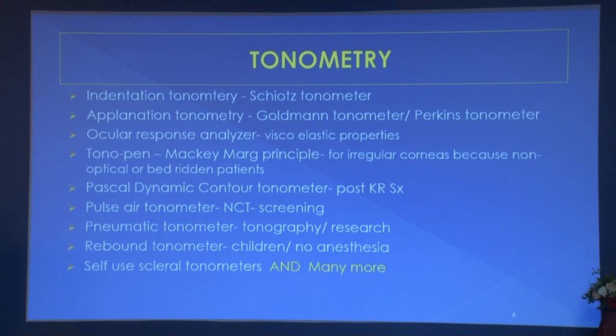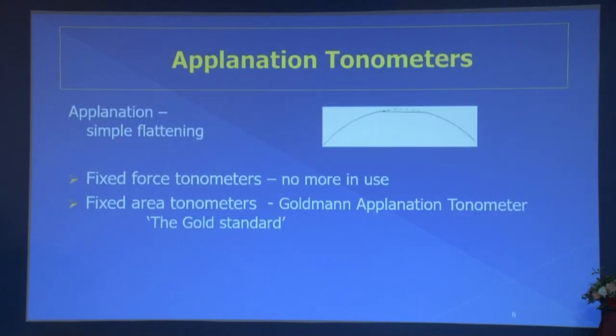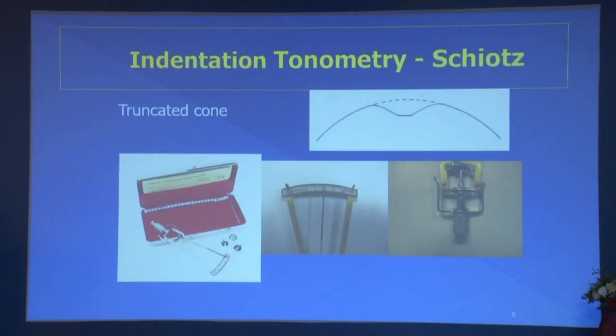Tonometry is basically indentation and applanation, though other types are now included. Many instruments are coming up with specific indications. For applanation tonometry, fixed force tonometers are no longer in use — only fixed area tonometers are used now, and the gold standard is Goldmann applanation tonometry. Indentation tonometry is problematic when scleral rigidity is very high or very low.